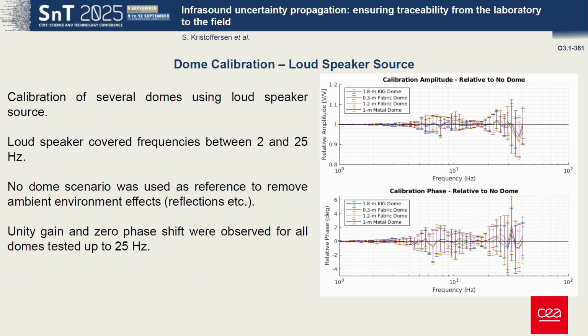And so now into some of this calibration. I did two calibration experiments. One was using a loudspeaker source. The loudspeaker was in a wooden baffle that gave sufficient back pressure area for it to generate an infrasound signal down to a few hertz.